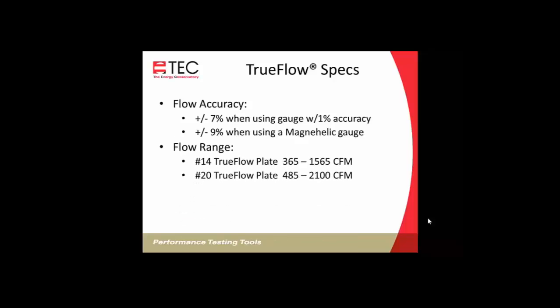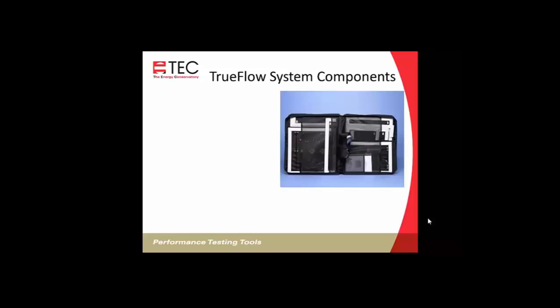The flow range, the number 14 TrueFlow plate, which is the size of it's 14 by 20. You can measure airflow 365 to 1565 CFM. And the larger plate, the 20 by 20, the number 20 TrueFlow plate, 485 to 2100 CFM. System weight is going to be about 13 pounds for the total system.